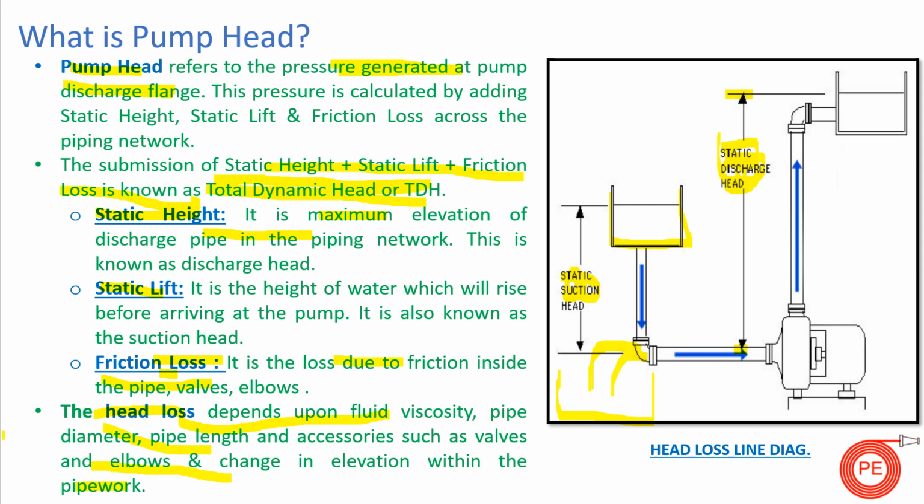So while calculating the head loss, we have to consider static suction lift, static discharge head, and all the frictional losses. By accumulating all these things and considering all these factors, we calculate the total head that will be generated by the pump, or the total head that is required at our system.